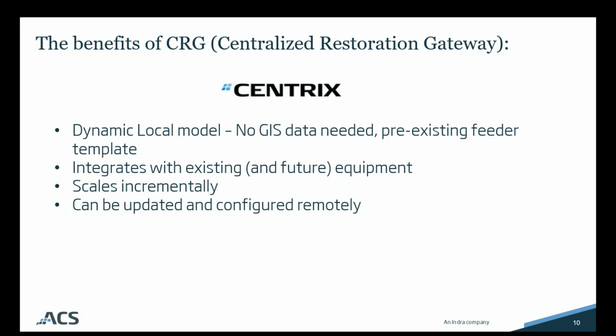So the benefits of this approach gave Georgia Power a dynamic local model. No GIS data is needed for this, and it's based on a pre-existing feeder template. It integrates with existing and future equipment, scales incrementally, and can be updated and configured remotely. So the system essentially isolates and restores within 1 to 2 minutes, instead of the, at the time, 15 minutes or longer it might take to determine the right switch plan using an OMS and manually switching from SCADA, for example. An even bigger impact was in areas without any automation at all.